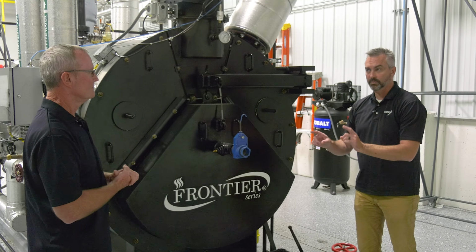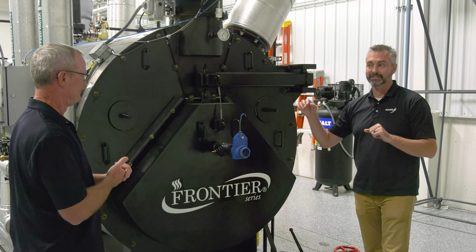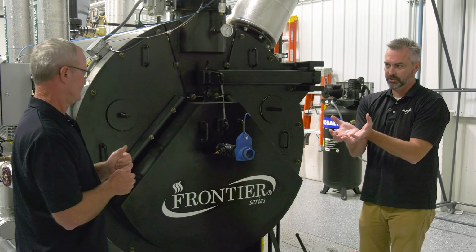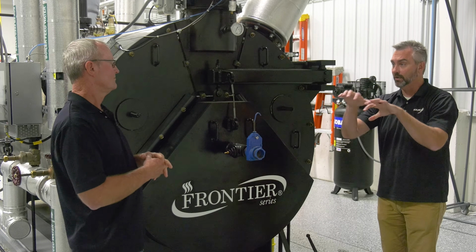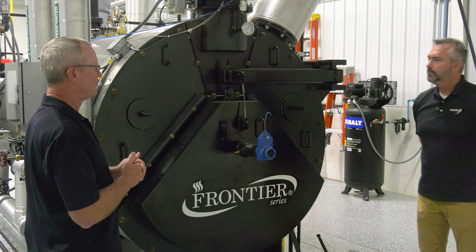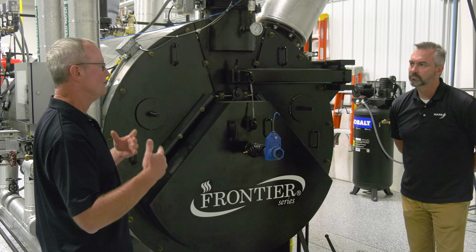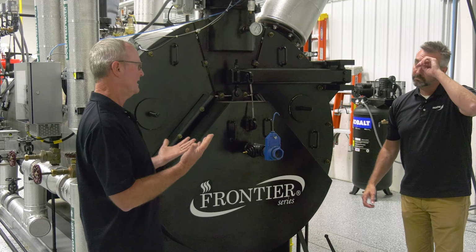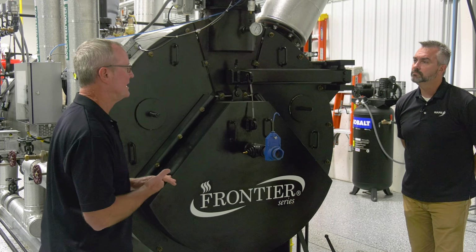Now, just so that we clarify, you said fire side. This is a fire tube boiler, so that means that the water is on the outside of the tubes. Yep. And so when you have the scale from the water, obviously that's going to be on the outside, it creates that insulation. Yep. And if it's a water tube boiler, just the opposite. The water's inside the tubes, fire's on the outside of the tubes, but you have the same issue. It's an insulating component that you can't have on the tubes. You've got to keep that off of there.